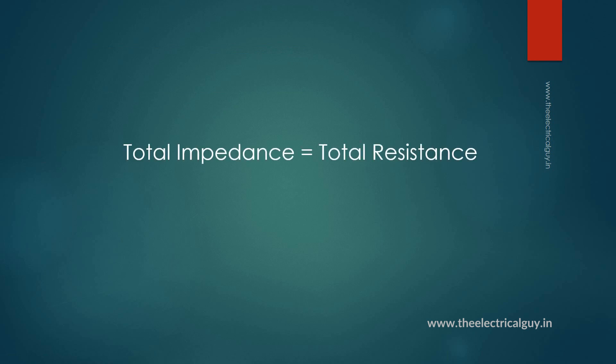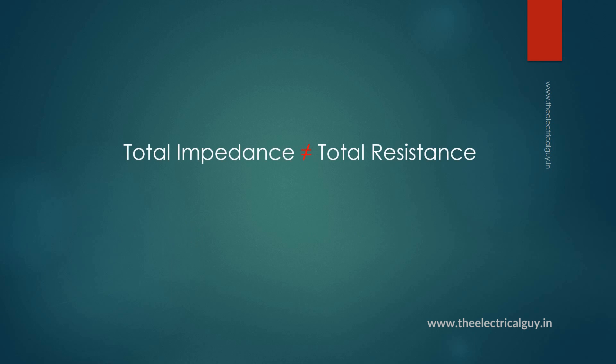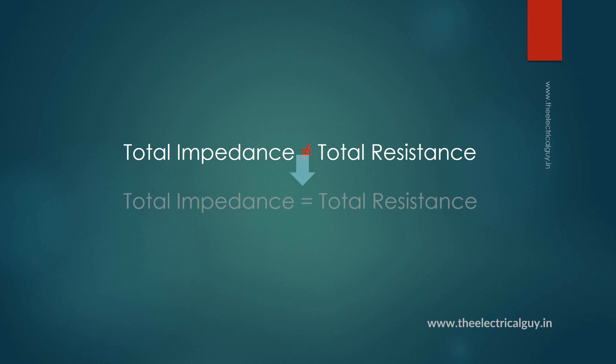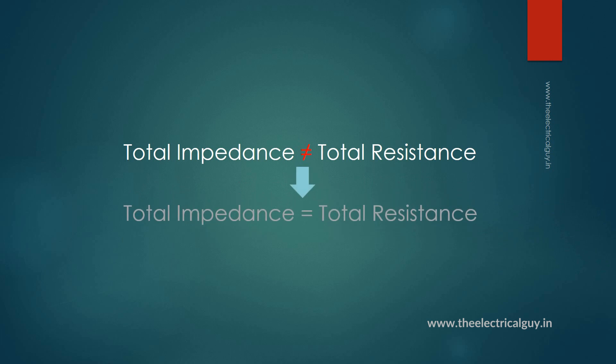If you understood this simple math, you have understood the concept of how you can improve power factor. If your system's total impedance is equal to total resistance, then it means your power factor is good and no reactive power is consumed. But as soon as you add load to it — the load most of the time is inductive — your total impedance is no longer equal to your total resistance, which means you are consuming reactive power and the power factor is poor. To get back to your original position where total resistance equals total impedance, you have to add an equal and opposite amount of reactive power to the system.